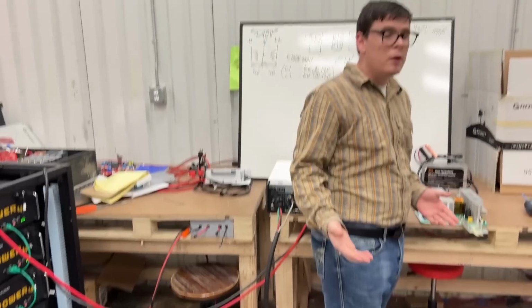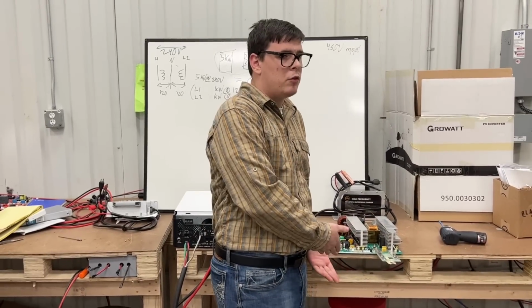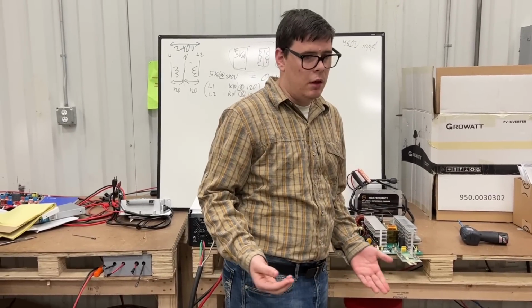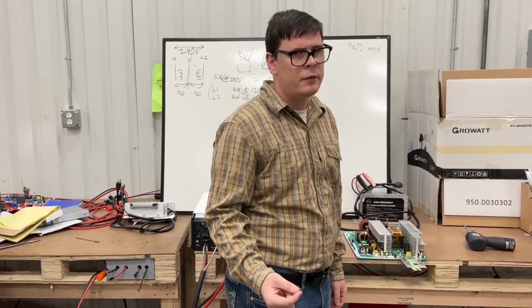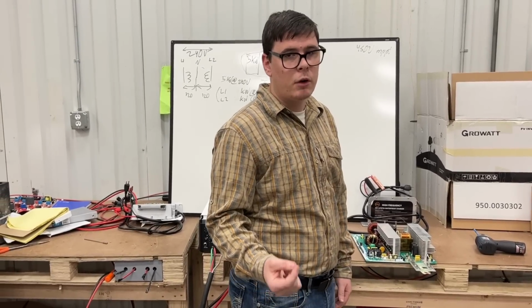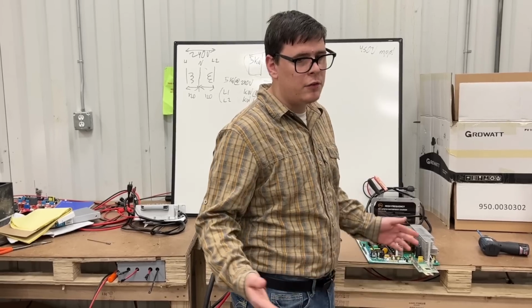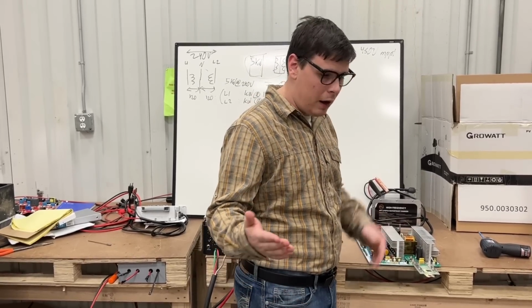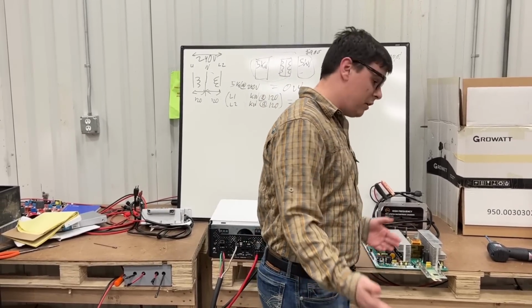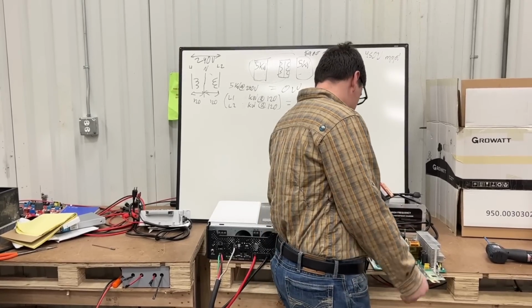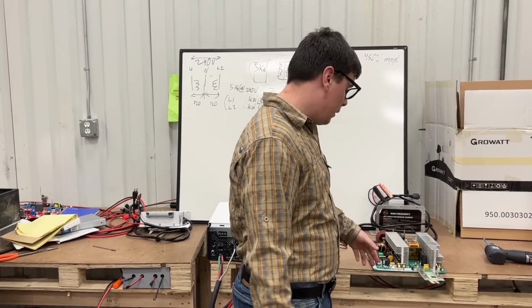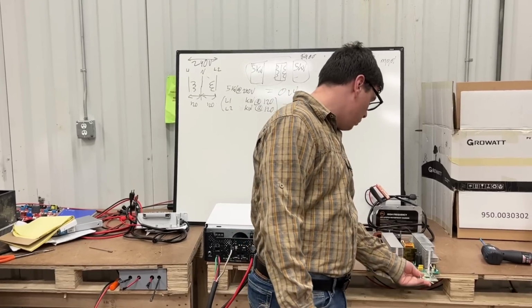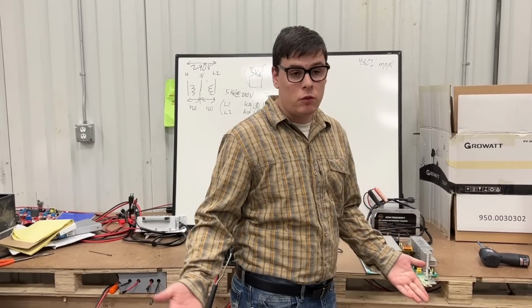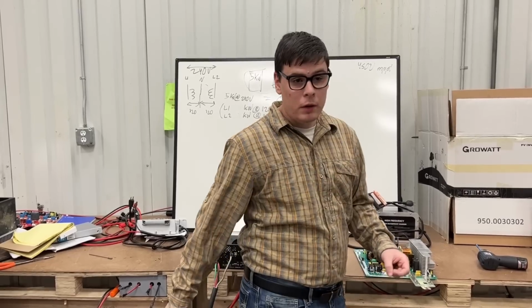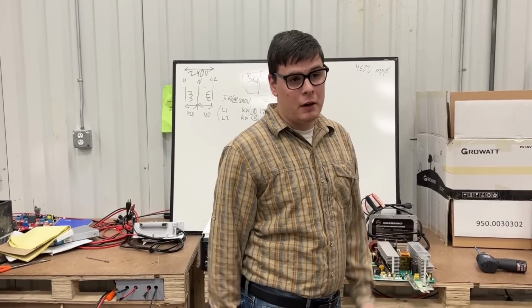I'll be honest with you, the bonded unit works in Europe, but frankly, you don't want this neutral ground bond in the United States. You're only supposed to have one neutral ground bond on your entire system, according to the NEC. So the way the U.S. does electrical bonding and grounding, it doesn't even make sense to have a bond. But with our boards, we actually bought the right unit. So there is no screw, and on the back side, there is no contactor.